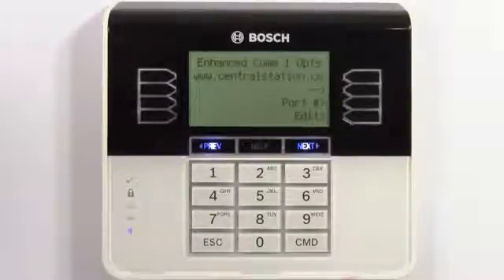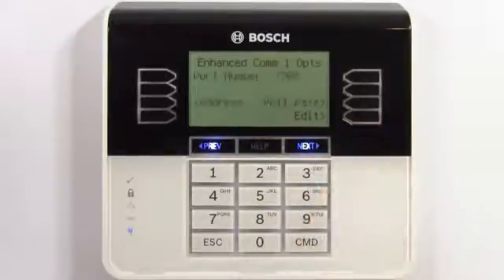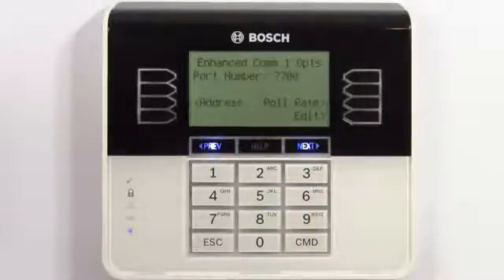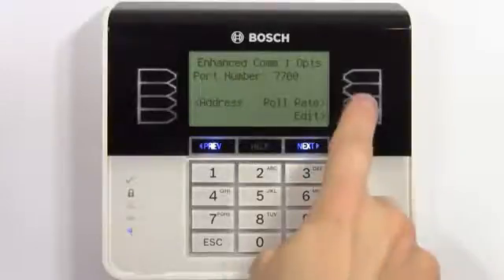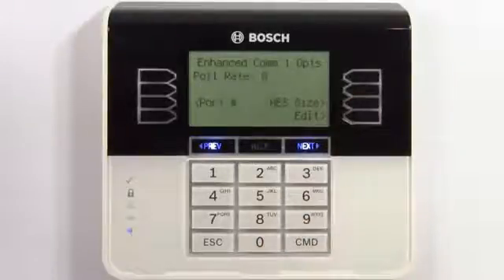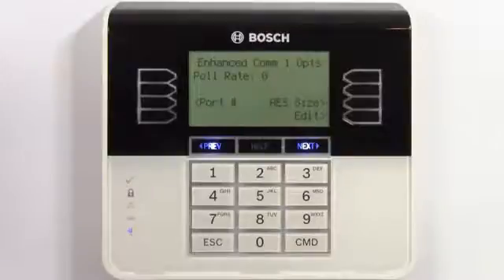Next, check the port number for your central station. 7700 is fine for our example. Select poll rate. Zero means this communication method is turned off, so we'll change it to 240 to meet UL standards.